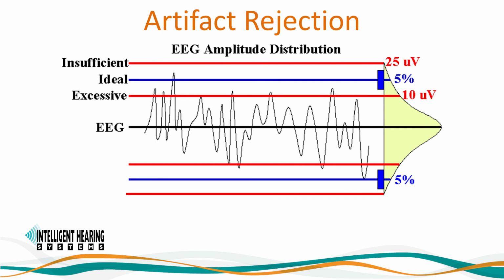Once you are ready for testing and have loaded your appropriate settings file with all your acquisition parameters, it is time to set the artifact rejection region. Artifact rejection is an amplitude-based technique and should be set appropriately depending on the EP type. The percentage varies and depends on the gain value used. Artifact rejection should be set such that only the largest 5 to 10% amplitude of the EEG is rejected. Note that many more sweeps will be needed to average out noise. Thus, it is important to begin the acquisition with low noise conditions.